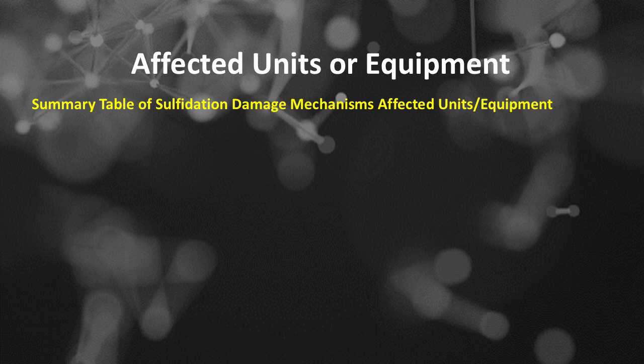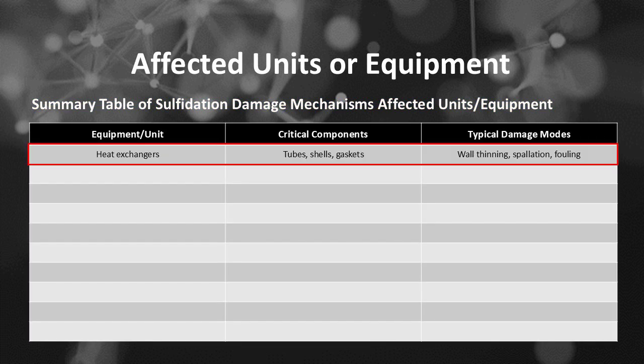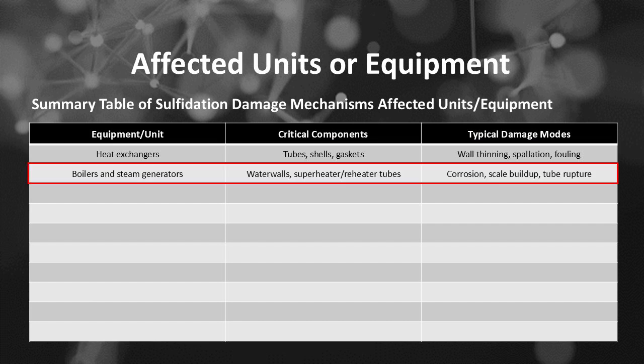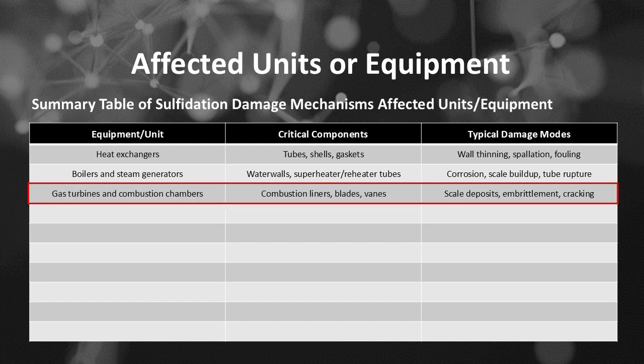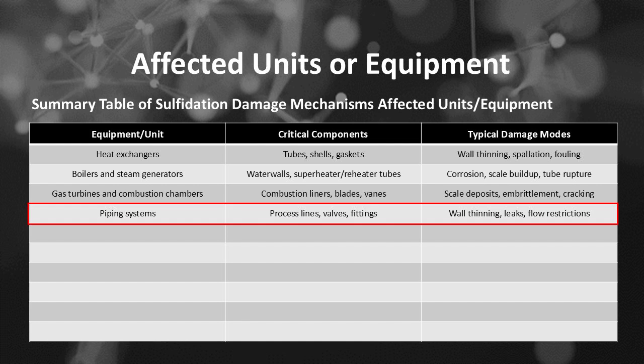Summary table of sulfidation damage mechanisms. Affected units and equipment. If the unit or equipment is heat exchangers, then its critical components are tubes, shells, and gaskets, and its typical damage modes are wall thinning, spallation, and fouling. Boilers and steam generators: water walls, superheater or reheater tubes; corrosion, scale buildup, tube rupture. Gas turbines and combustion chambers: combustion liners, blades, vanes; scale deposits, embrittlement, cracking. Piping systems: process lines, valves, fittings; wall thinning, leaks, flow restrictions.